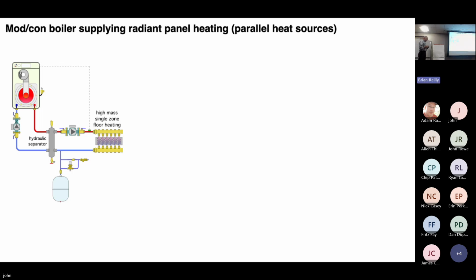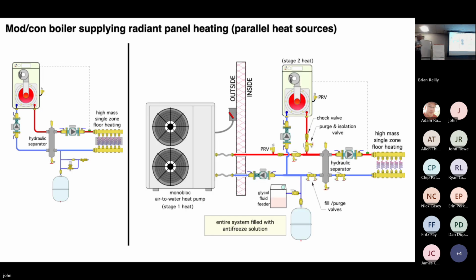But ECM technology, the variable speed permanent magnet circulators, are becoming more and more dominant in the market. And a magnet in the bottom of the hydraulic separator will catch magnetite, and that prevents it from collecting in the circulator, or for that matter, in the boiler or anywhere else in the system. So we're going to convert that over to this. Okay.